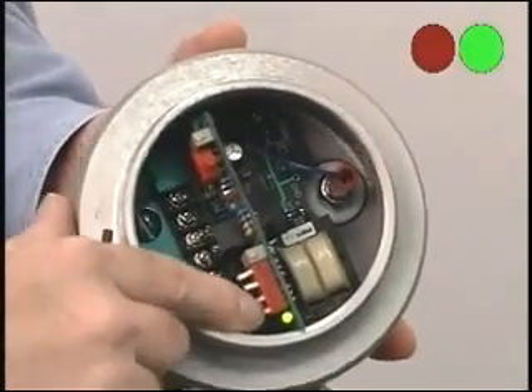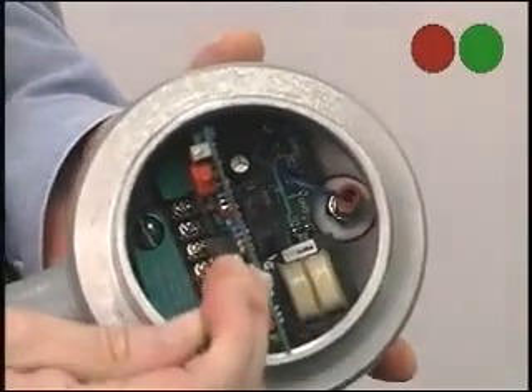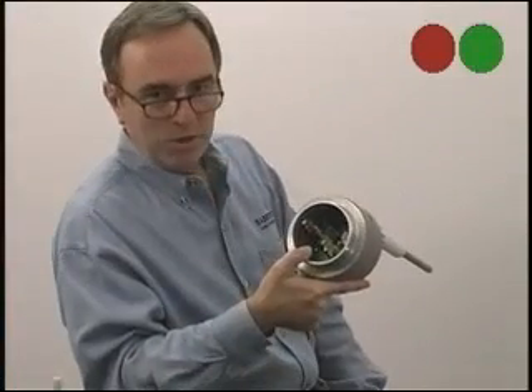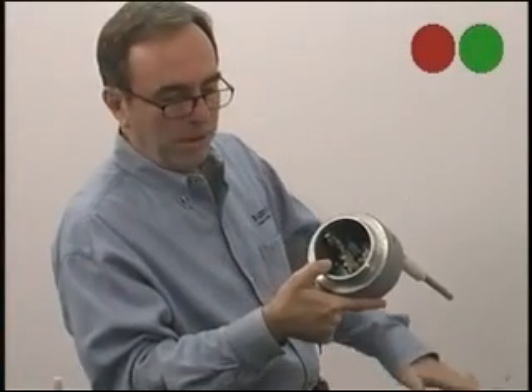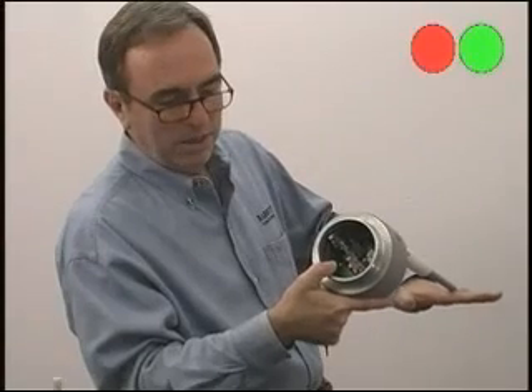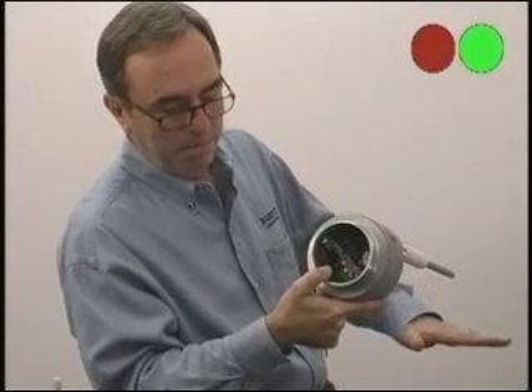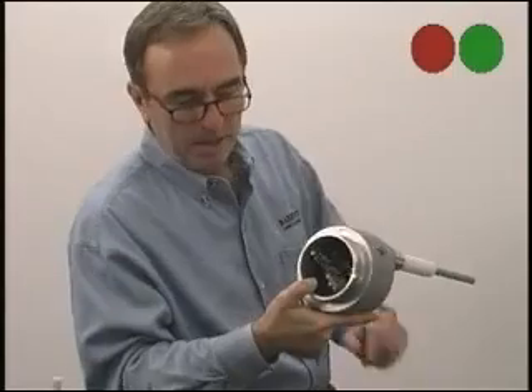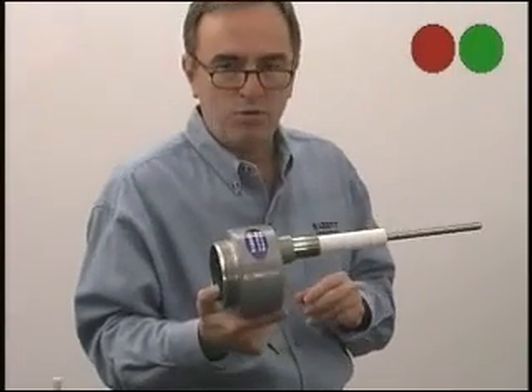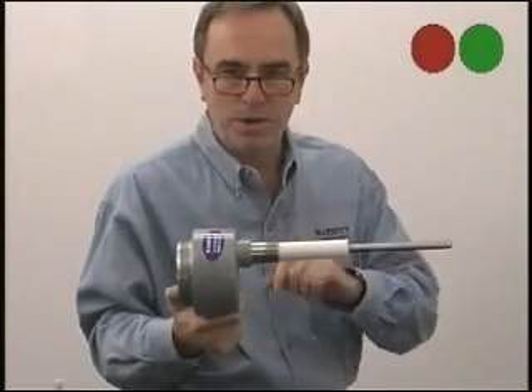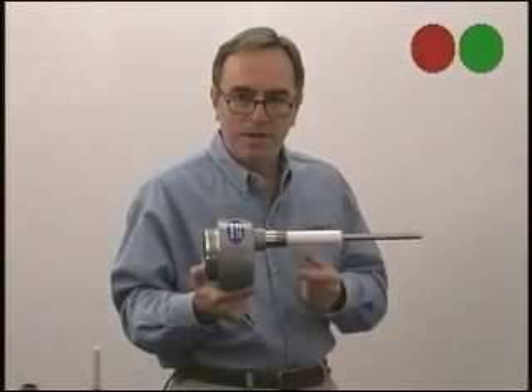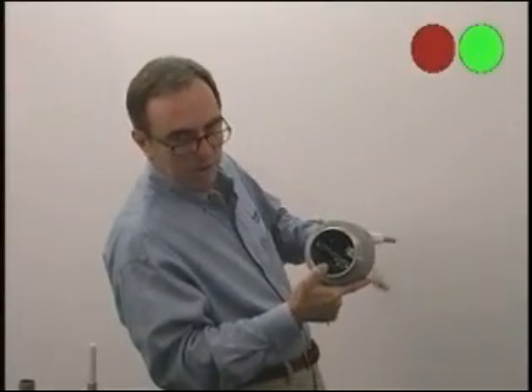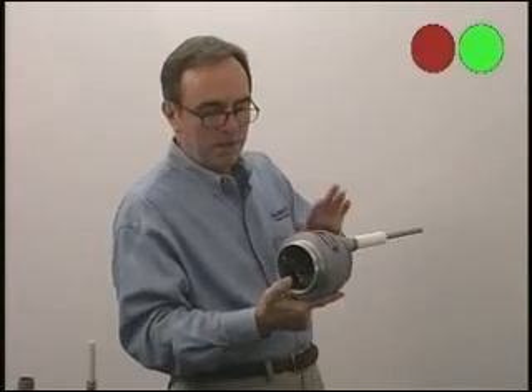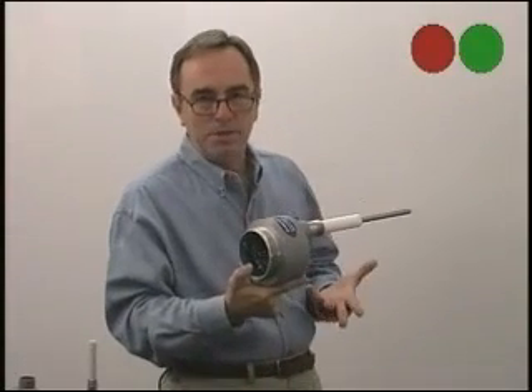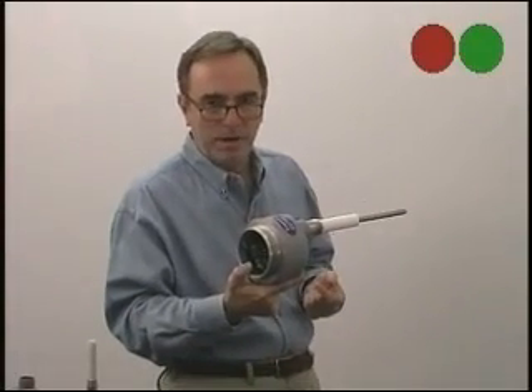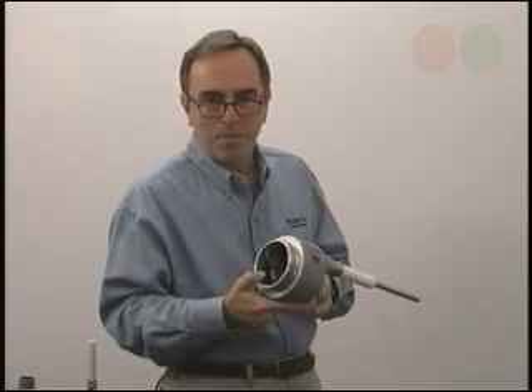If you flip these two switches down, it becomes an instant on, time off. So you could use it to pump down a sump. The fluid level would rise when it touches the probe, instantly turns on your pump, and then it pumps down for a certain period of time. Some people use this timer mode also for dry pump protection. They'll put a short probe in front of a pump, and every time a slug of fluid comes by, it resets a timer. If the timer ever times out, it indicates the pipe is drained, the pump is fixing to run dry. These units are in stock for immediate delivery.